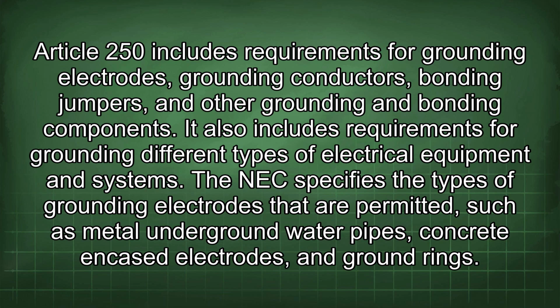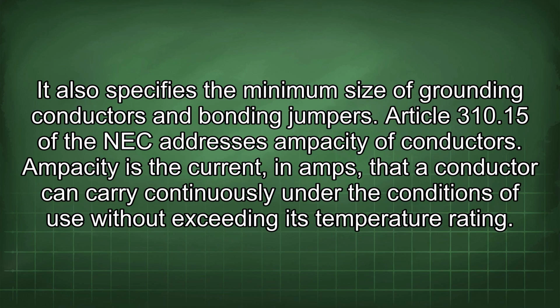Article 250 includes requirements for grounding electrodes, grounding conductors, bonding jumpers, and other grounding and bonding components. It also includes requirements for grounding different types of electrical equipment and systems. The NEC specifies the types of grounding electrodes that are permitted, such as metal underground water pipes, concrete encased electrodes, and ground rings. It also specifies the minimum size of grounding conductors and bonding jumpers. Article 310.15 of the NEC addresses ampacity of conductors.